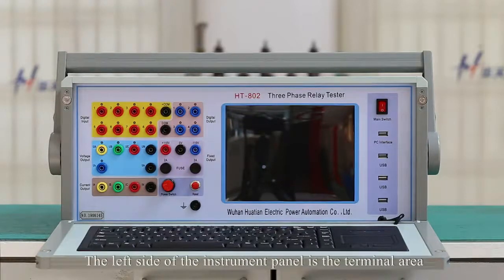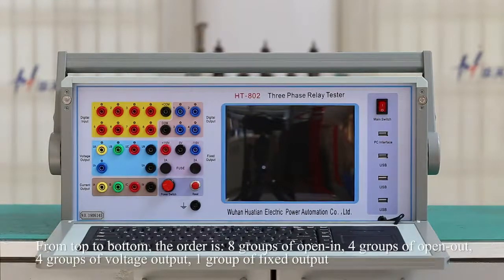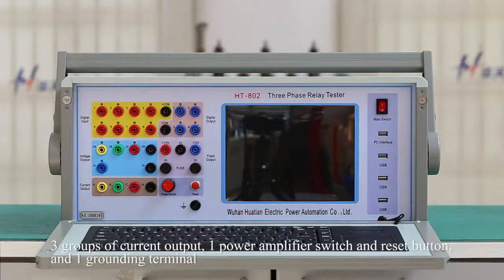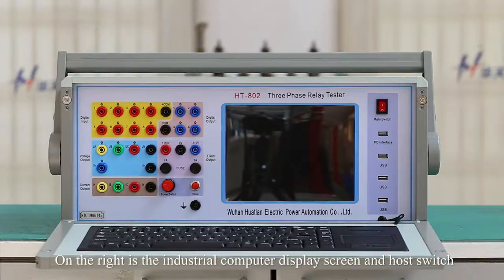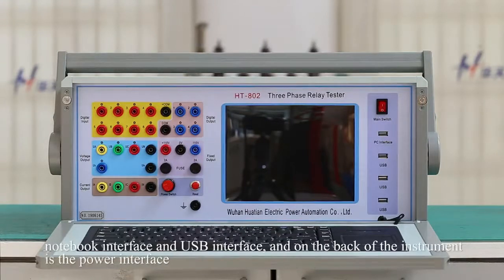The left side of the instrument panel is the terminal area. From top to bottom, the order is 8 groups of open in, 4 groups of open out, 4 groups of voltage output, 1 group of fixed output, 3 groups of current output, 1 power amplifier switch and reset button, and 1 grounding terminal. On the right are the industrial computer display screen and host switch, notebook interface, and USB interface. On the back of the instrument is the power interface.